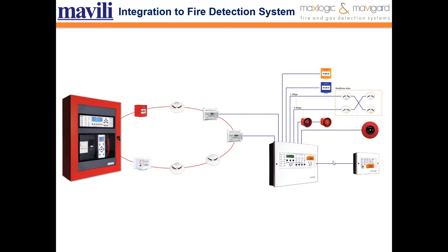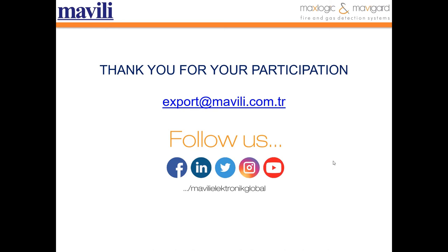Let's talk about integration with the fire detection system. If a gas extinguishing system is installed in a building that already has a detection and warning system, the alarm and fault outputs of the extinguishing system are connected to the fire alarm system and monitored with separate zone indicators. It is connected to fire detection systems with fire and fault relays on the extinguishing system and can be monitored as a separate zone.